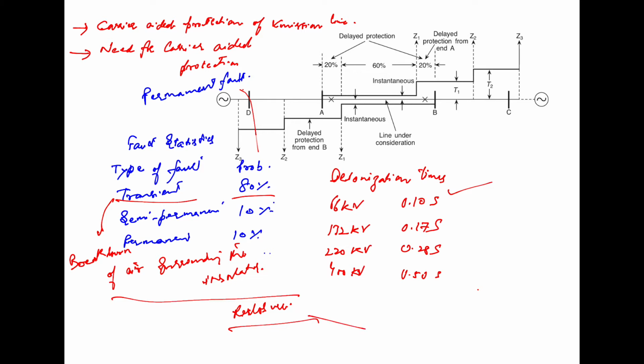Now, if the fault is a permanent one, the recloser will be unsuccessful. So in case of a permanent fault, this recloser would be unsuccessful. That is, the protective relay will immediately cause the circuit breaker to trip, because the relay will sense that the fault persists.